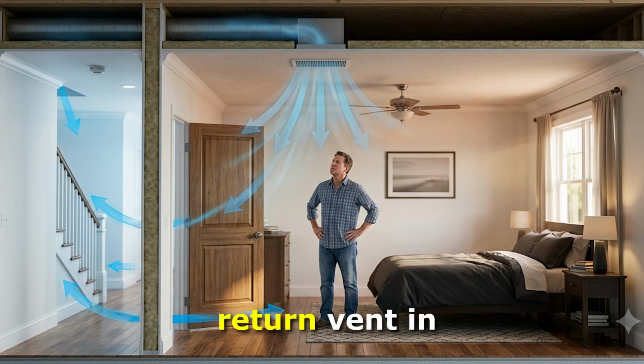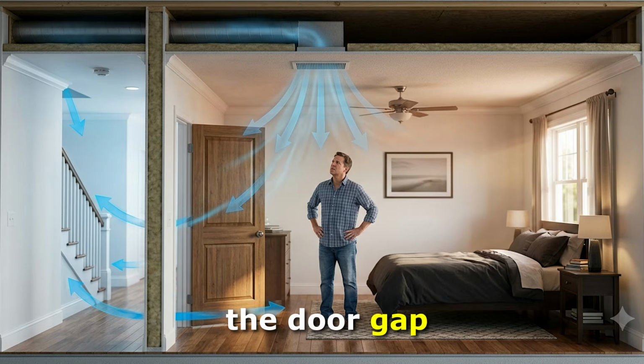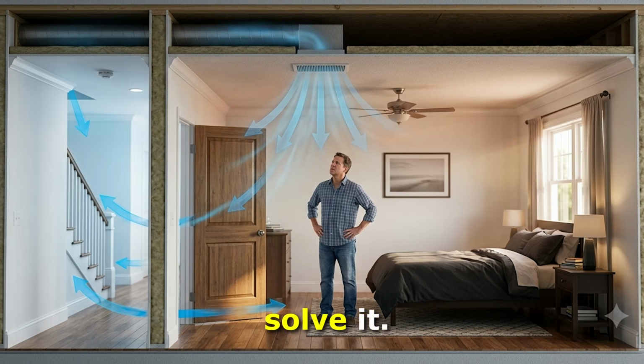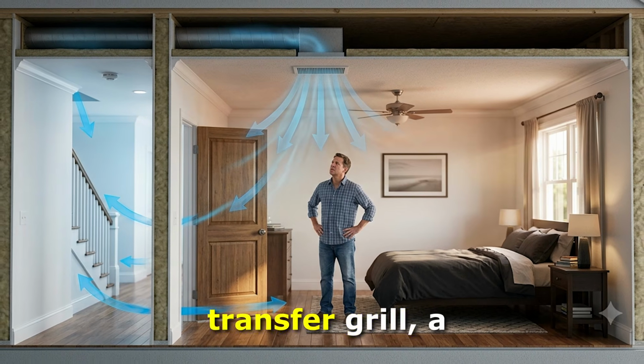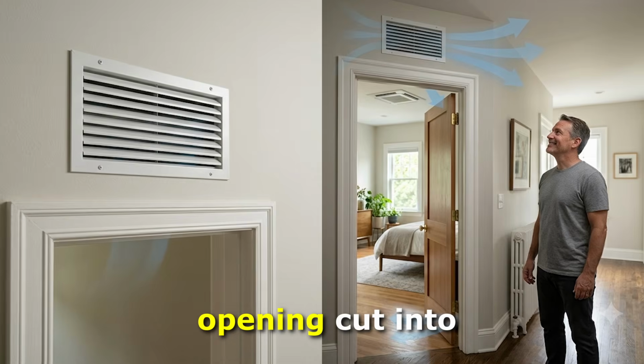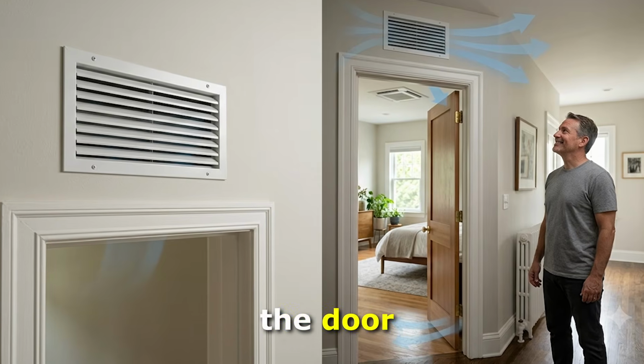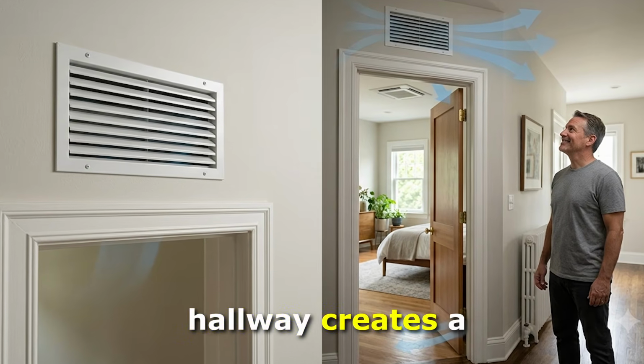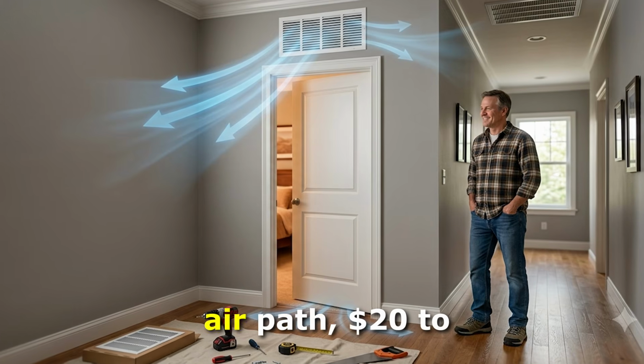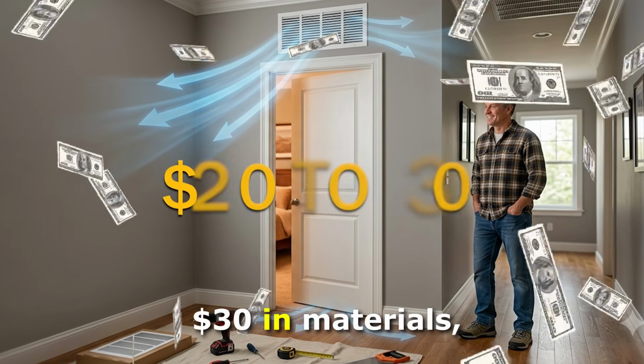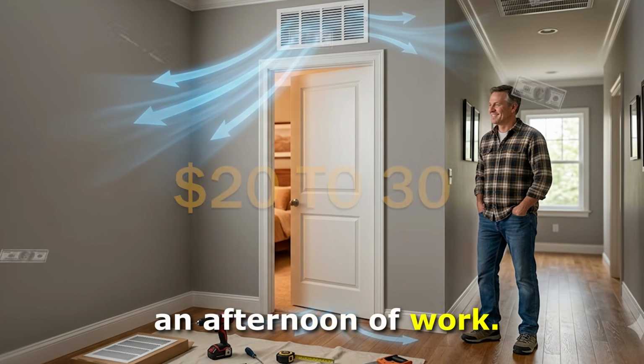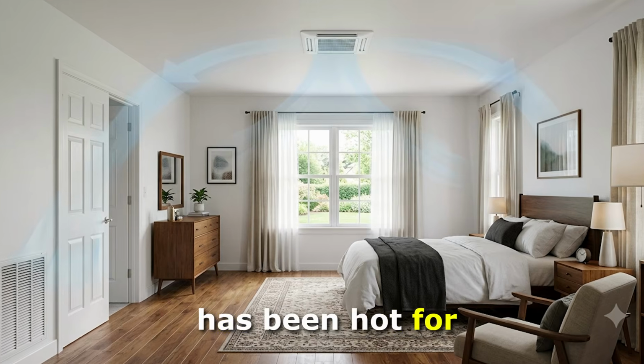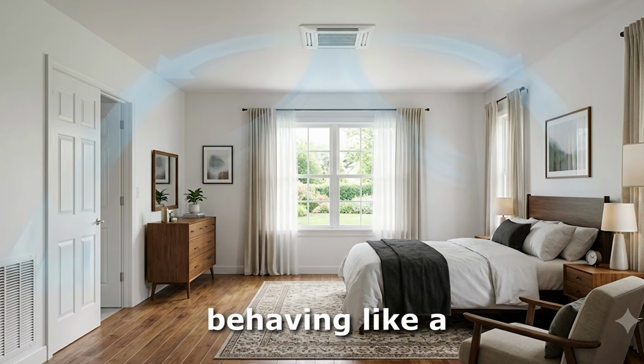If there is no return vent in the room at all, the door gap helps but may not fully solve it. In that case, a transfer grill, a small louvered opening cut into the wall above the door connecting the room to the hallway, creates a permanent return air path, $20 to $30 in materials, an afternoon of work, and a room that has been hot for years starts behaving like a normal room.